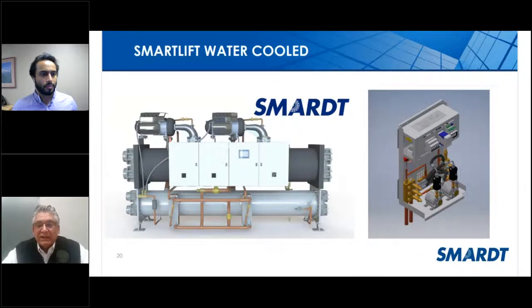Also, the other portion of that is that it helps with high lift. Anytime you have low entering condenser water in a design leaving water temperature, you have to be concerned about the difference between entering condenser water and leaving chill water. Typically, that's about a 12 degree difference between entering condenser water and leaving chill water. Smardt has solved that problem on these new oilless bearing machines, because we use a refrigerant pump to alleviate that problem. So now you can get as low as 50 to 55 degree entering condenser water with a 44 degree leaving water. A great advance in the technology, and you can utilize lower entering condenser water to increase efficiencies during part load as well.